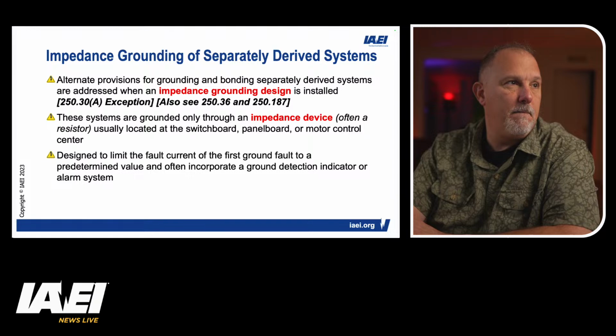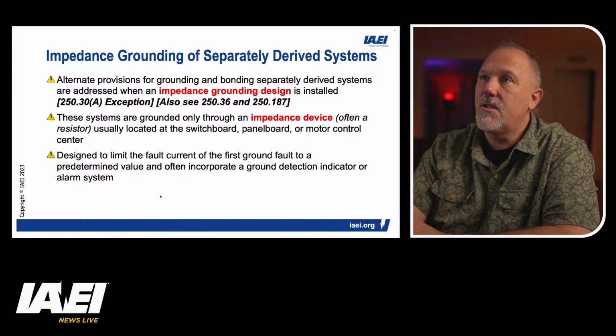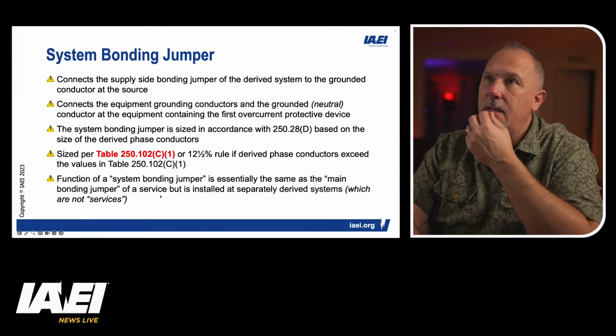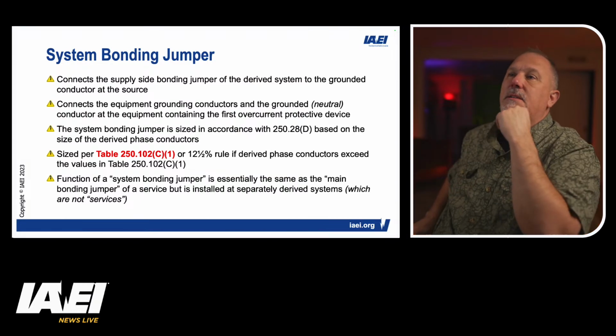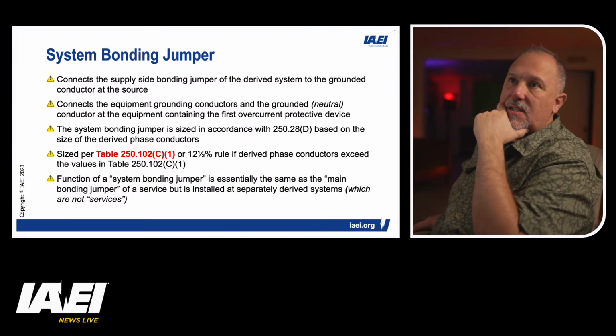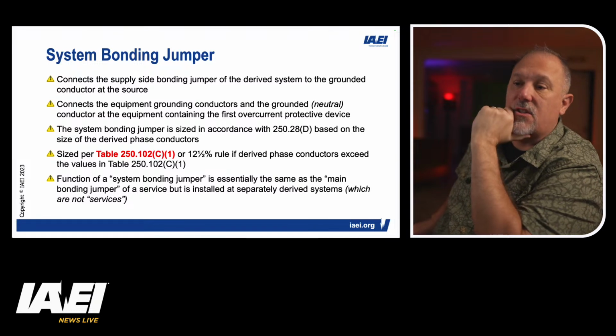Let's go back to this. The system bonding jumper connects the supply side bonding jumper of the derived system to the grounded conductor at the source.